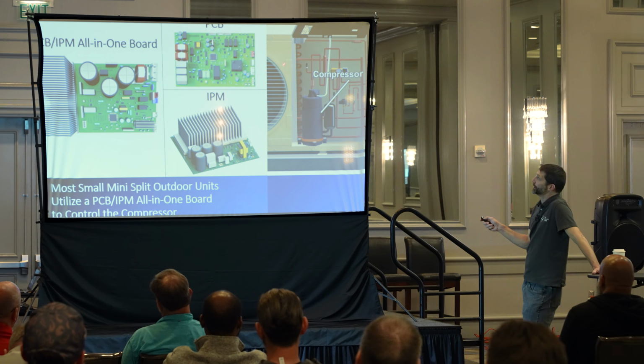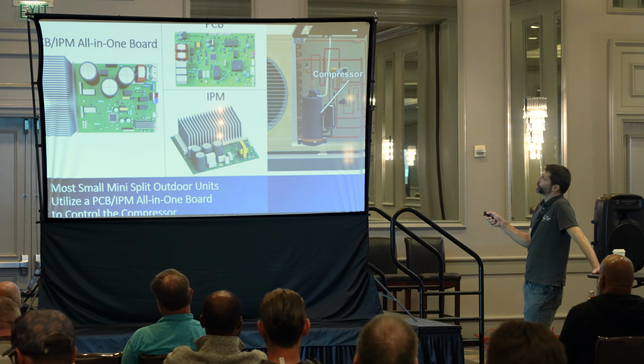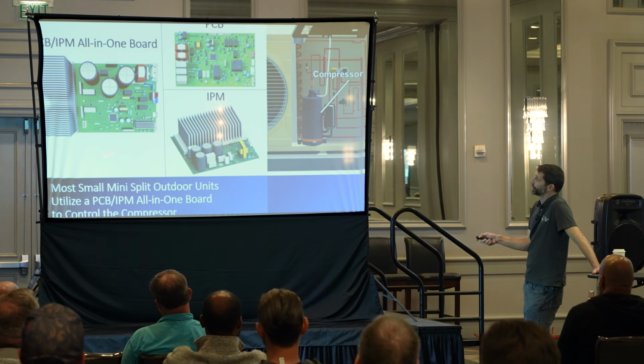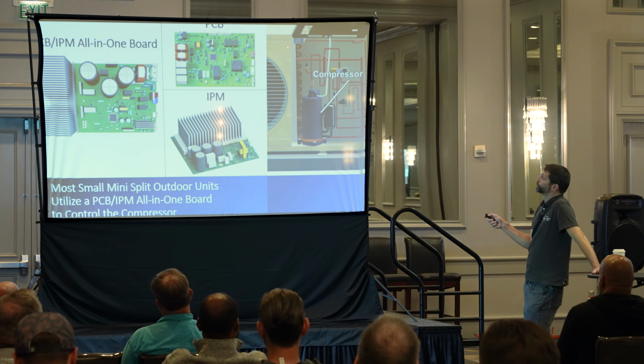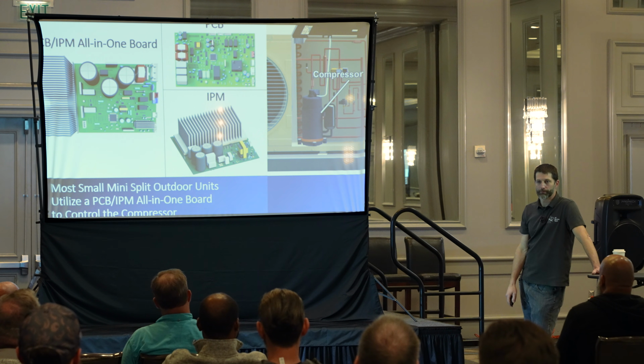It's between the fan and the coil, and if you allow it to get too much dust on it, you're not going to have airflow going across the little aluminum heat sink. The circuit board is going to fail just due to a preventative maintenance problem.